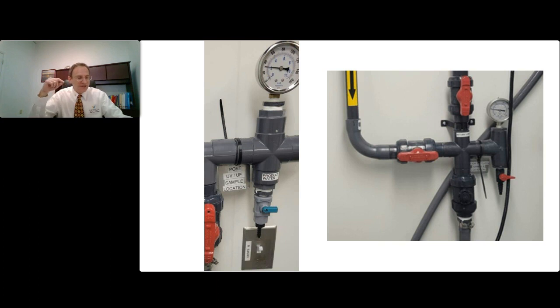So while the AAMI TIR34 recommended no more than 6 times the pipe diameter for dead legs and branches that did not run continuously, connections to equipment like the ultrasonic dropped from a recirculation loop that was in the ceiling 10 feet up, down to the floor, which then connected to a 6-foot stainless steel braided hose, which then connected to the ultrasonic. So 16 feet of dead leg when the pipe diameter said you should have had no more than 6 inches. Lastly, the system was not being regularly disinfected.